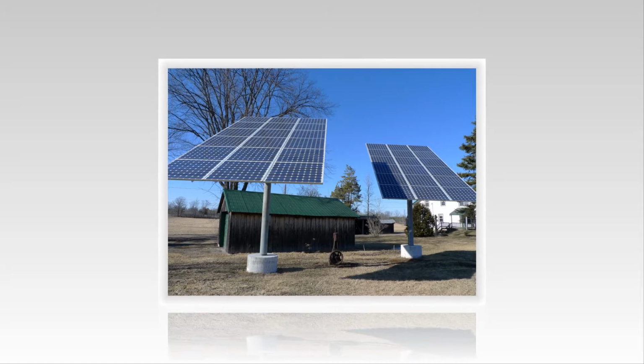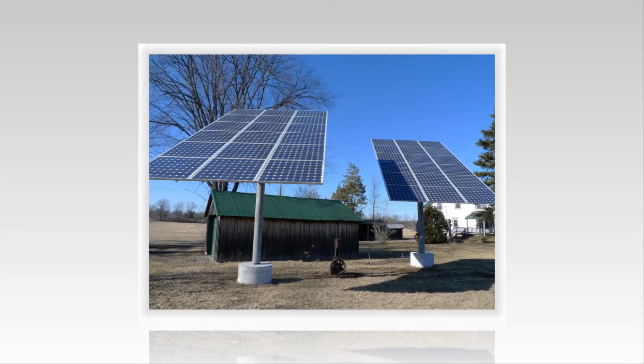Calculations for net metering facility with 1 kW solar. At least 110 square feet of shadow-free empty space is required for installation, whose cost would be Rs 65,000. This would also be eligible for 30% government subsidy, which would be equivalent to Rs 19,500. Hence the beneficiary's 70% share would amount to Rs 45,500. The cost of net meter would be borne by the consumer, around Rs 1,500 per kilowatt.